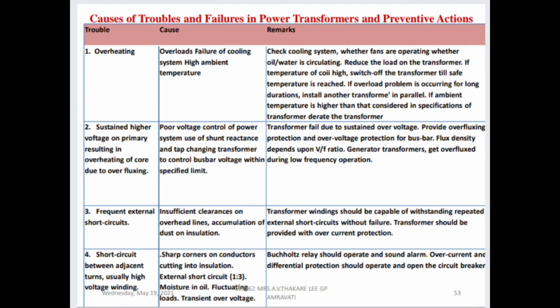Hello. So this is part five of this unit, testing and troubleshooting of transformer. In the last lectures we saw the types of tests on the transformer, then the routine test, supplementary test, back to back test, and the causes of failure. So now we see the troubleshooting charts. First overheating: sustained higher voltage of primary resulting in overheating of core due to overfluxing. Then the third point is the frequent external short circuit.